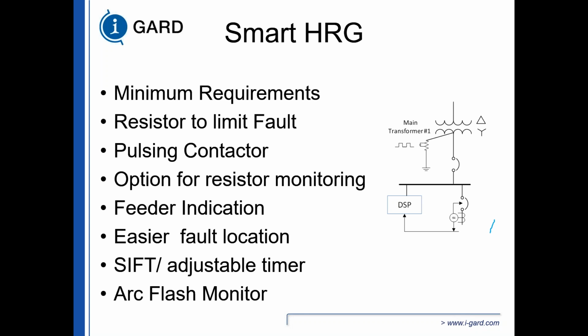And we can have an arc flash monitor. At I-Gard, we listen to what our customers say. And our customers sometimes say that, ideally, I like the high resistance ground system, and I like the idea that you can have a lower probability of having an arc flash. However, I want to have my cake and eat it too. So not only do I want to have a lower probability of having an arc flash, I also want to have a lower incident energy level.